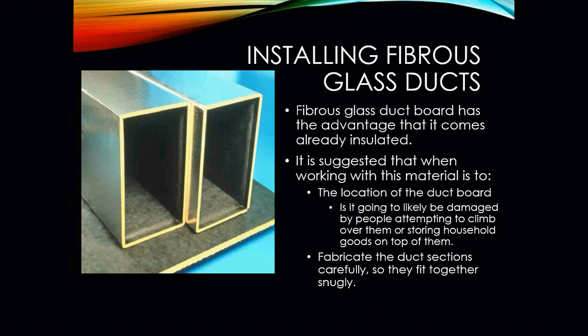This type of ductwork does have advantages as it comes already insulated, as you can kind of see in this picture here. There's the insulation. It already has a silver coating on the outside, which is meant to reflect the heat so that it doesn't get absorbed into the ductwork. It is suggested that when working with this type of material, it is to be used in an area where it is likely not to be damaged.